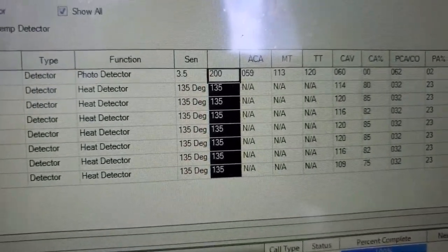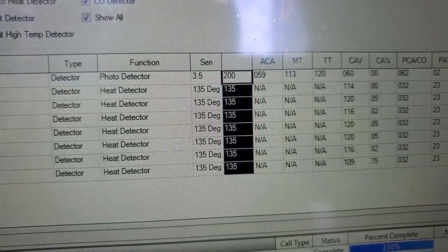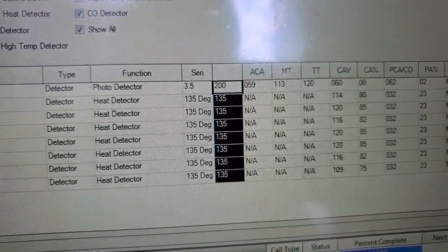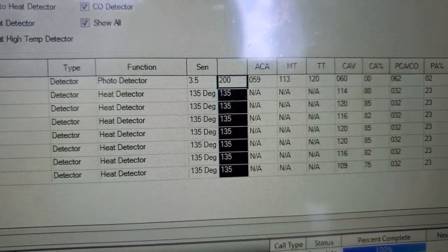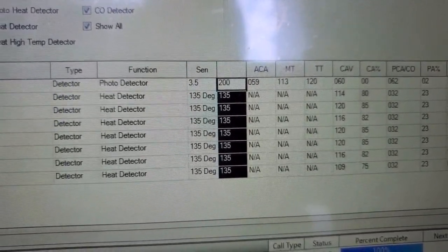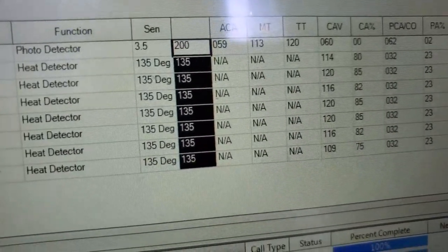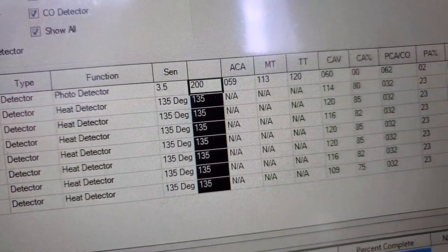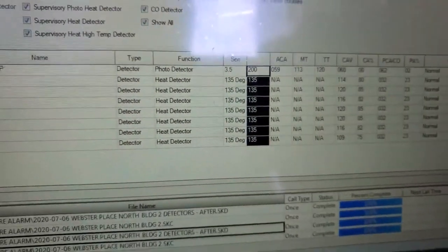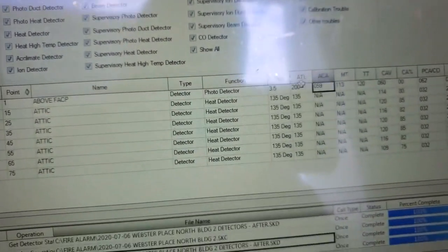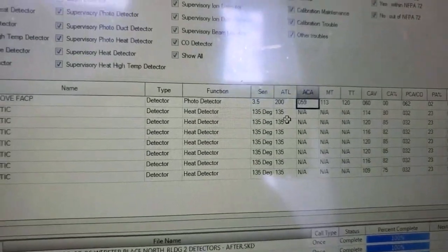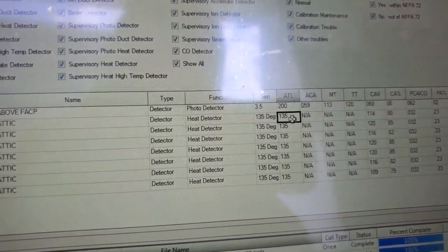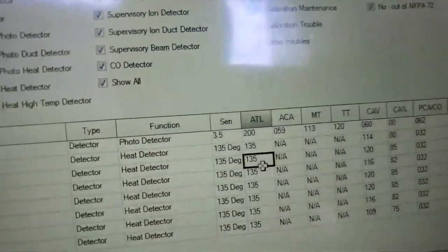So this is with regular heat detectors, SK heats. And in the sensitivity column on the zone, I have it set at 165, but as you see here, it says 135. And this next column here, the ATL alarm temperature, is probably what that is. So that's saying that the alarm temperature is 135.